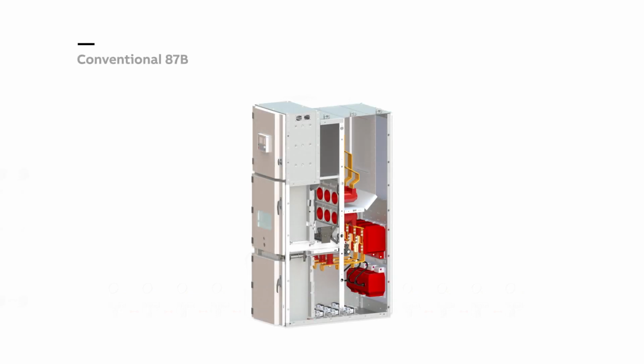Now, let's have a look at an example. Here we have a Unigear ZS1 medium voltage switchgear panel. This is the side view of the panel, where you can see inside the switchgear and its conventional instrument transformers. In case of 87B, there would be another set of CTs. The first set of CTs are used for current protection of the panel, and the second set for the 87B signal to the 87B relay, so the depth would be about 20% more.